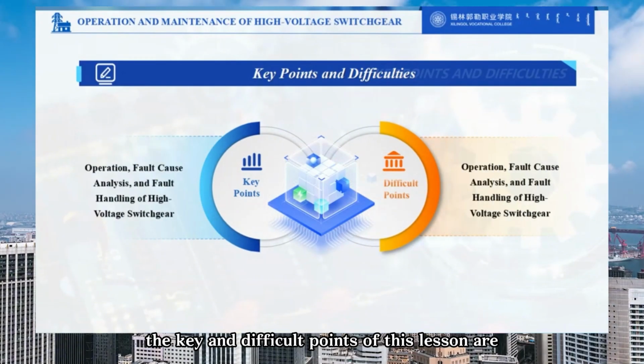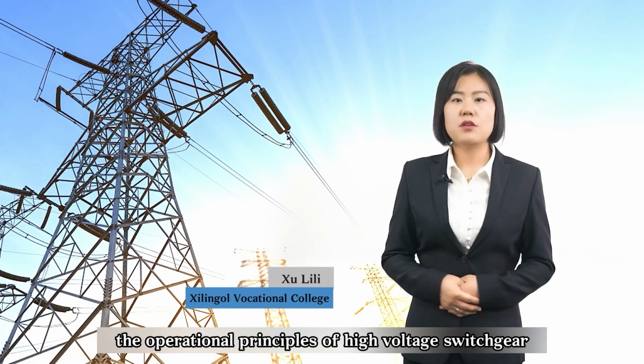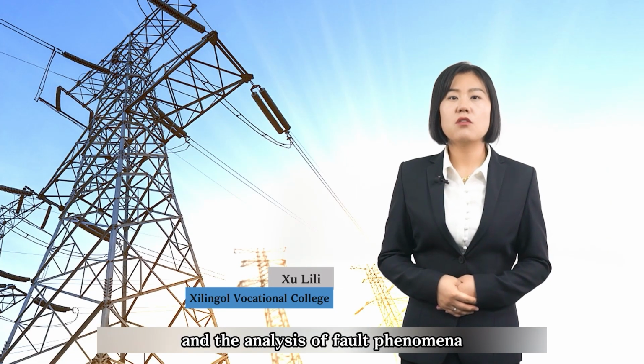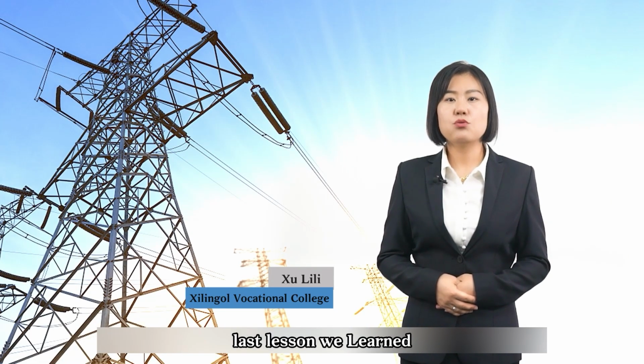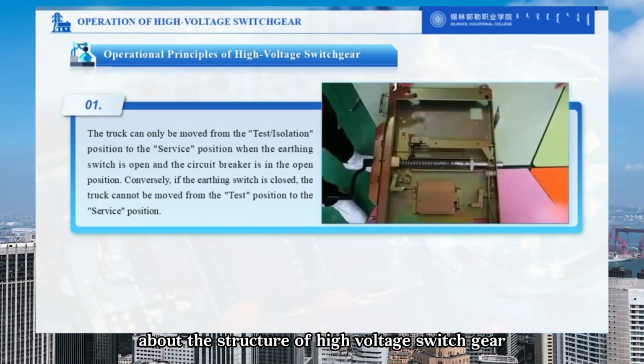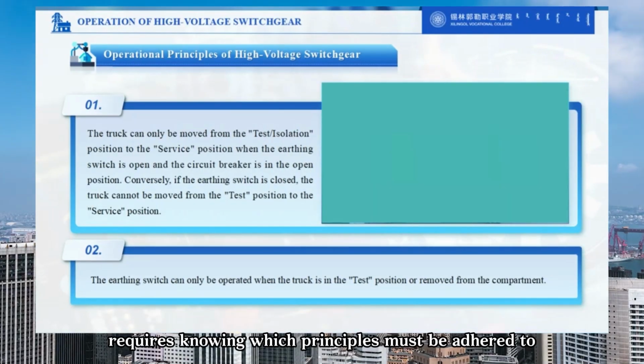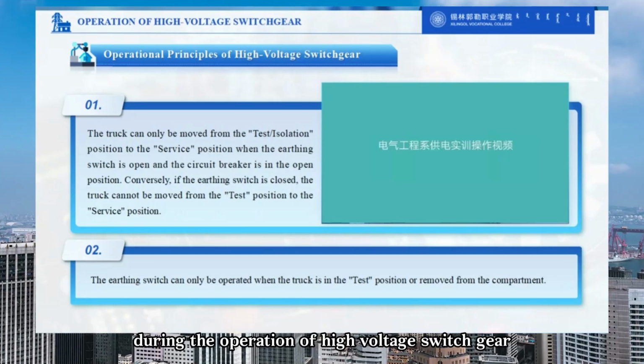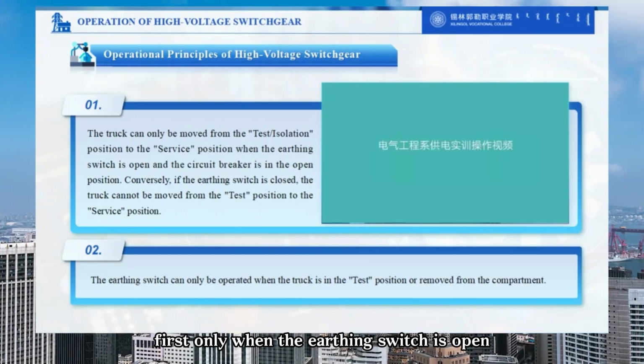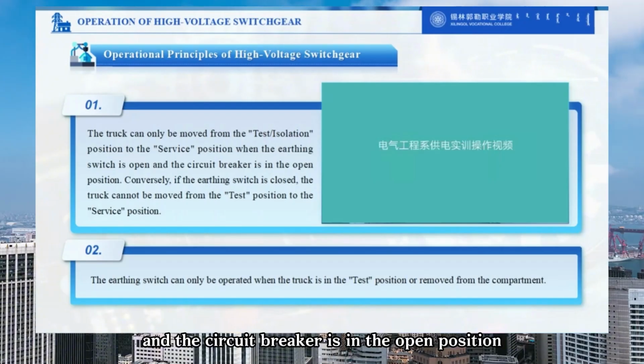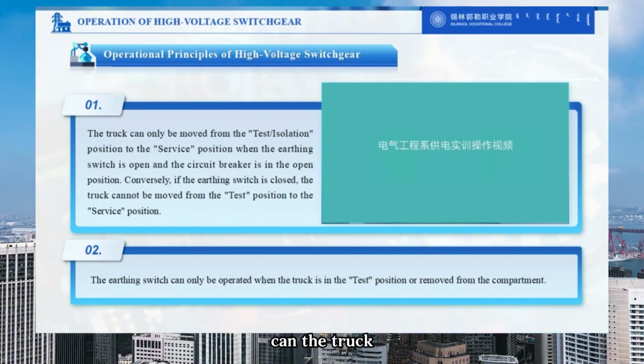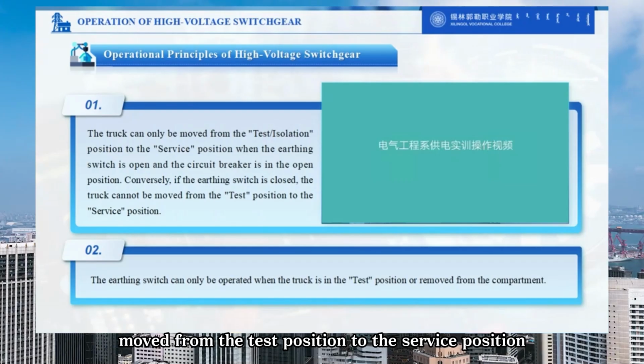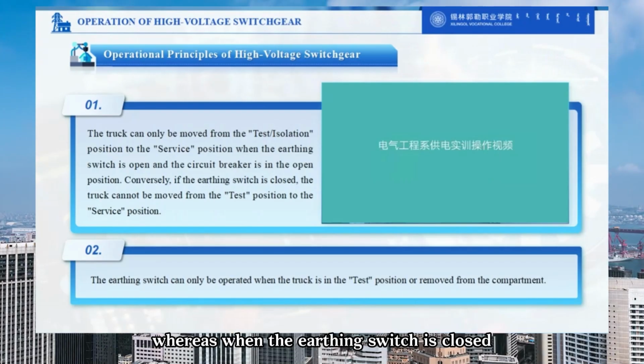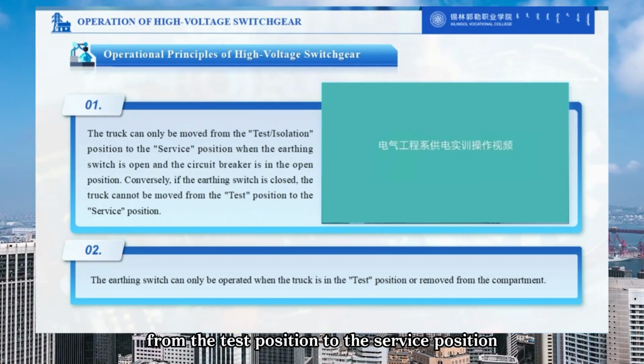The key and difficult points of this lesson are the operational principles of high voltage switchgear and the analysis of fault phenomena. Last lesson, we learned about the structure of high voltage switchgear. This lesson requires knowing which principles must be adhered to during the operation of high voltage switchgear first. Only when the earthing switch is open and the circuit breaker is in the open position can the truck or carriage be moved from the test position to the service position, whereas when the earthing switch is closed, the truck cannot be moved from the test position to the service position.